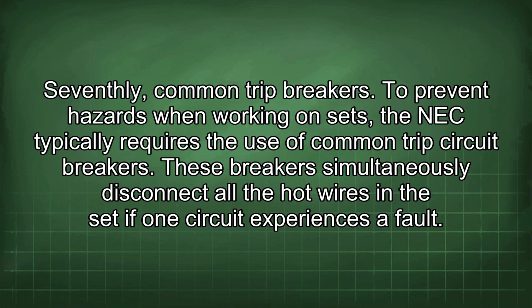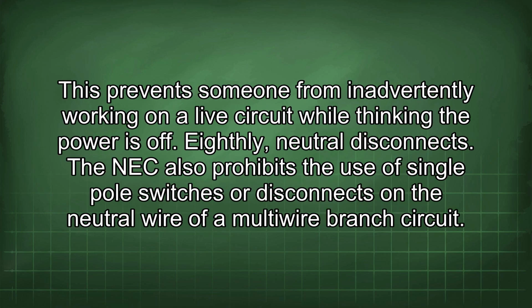Seventhly, common trip breakers. To prevent hazards when working on sets, the NEC typically requires the use of common trip circuit breakers. These breakers simultaneously disconnect all the hot wires in the set if one circuit experiences a fault. This prevents someone from inadvertently working on a live circuit while thinking the power is off.